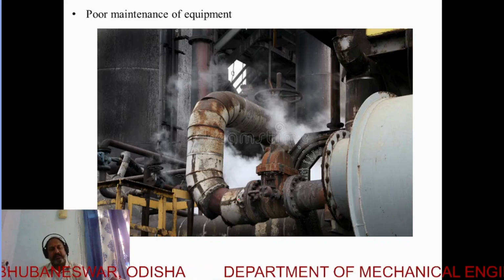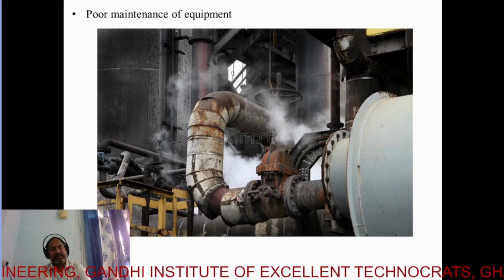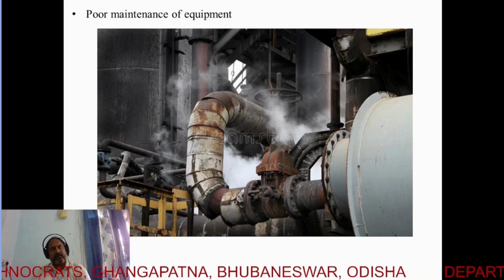The root causes might be a lack of routine pressure and leak testing, and a failure to inspect and replace the gaskets and seals wherever required. Here they have ignored the signs of corrosion, and they have delayed repair or any kind of replacement of the parts.